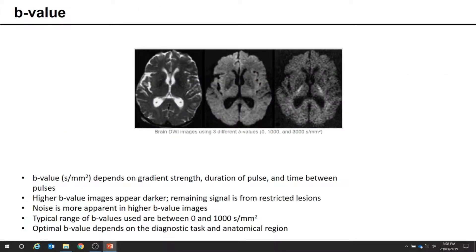The diffusion gradient conditions are described by a term called B value, which has units of seconds per millimeter squared. This depends on the gradient strength, the duration of the pulse, and the timing between those pulses. The actual formula for the B value depends on the shape and design of the gradient pulse and varies between vendors, but what the vendor will display is this B value.